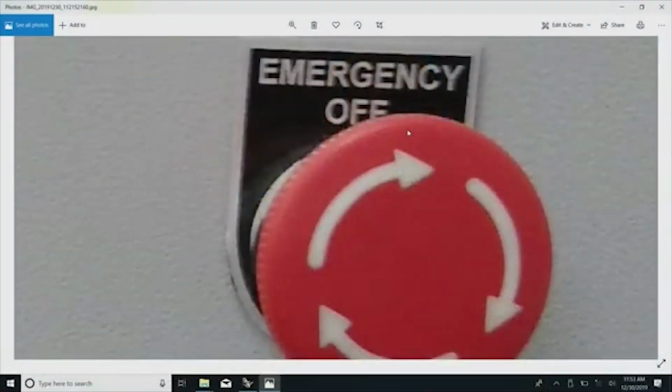And further, if you press this knob in, it stays pressed. You understand, everything is isolated through a huge contactor, everything switches off and it stays pressed by itself. You can't press it again and release it like that. There they have given another safety precaution: if you now turn it anti-clockwise, I am sorry, let me put it the other way, it has locked itself in the anti-clockwise position. If you turn it clockwise, it will pop out.